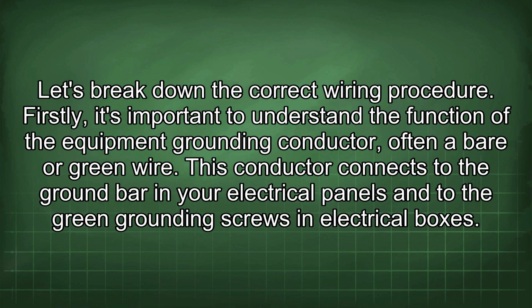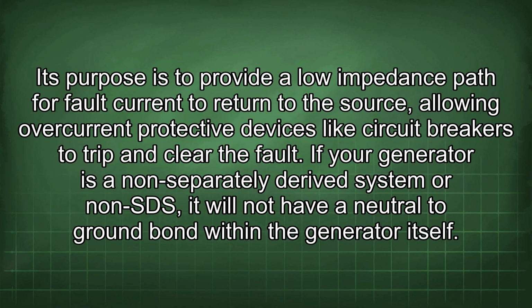Firstly, it's important to understand the function of the equipment grounding conductor, often a bare or green wire. This conductor connects to the ground bar in your electrical panels and to the green grounding screws in electrical boxes. Its purpose is to provide a low impedance path for fault current to return to the source, allowing overcurrent protective devices like circuit breakers to trip and clear the fault.